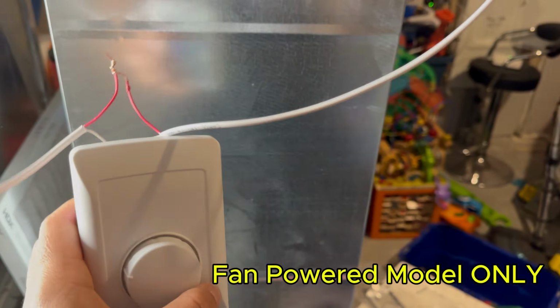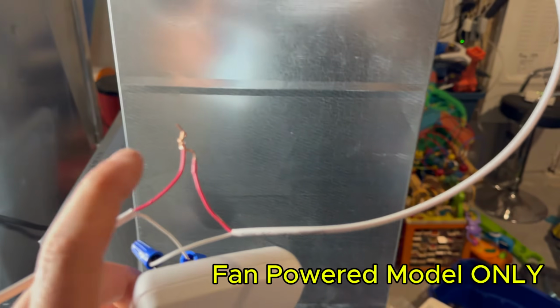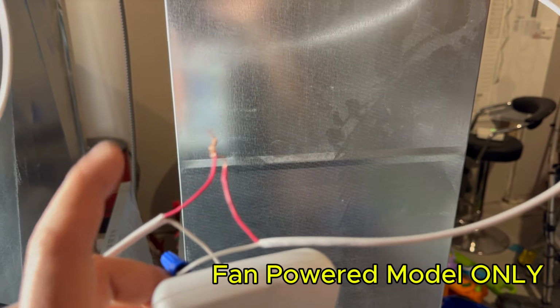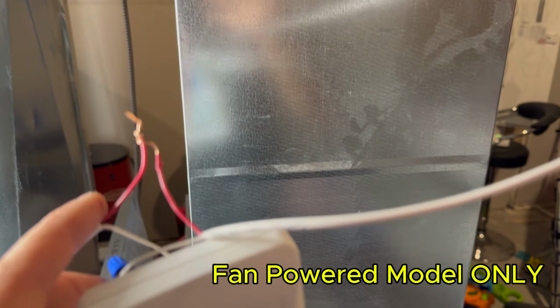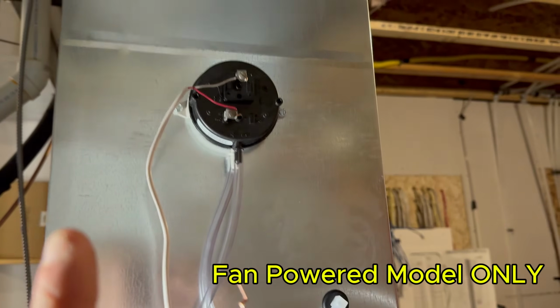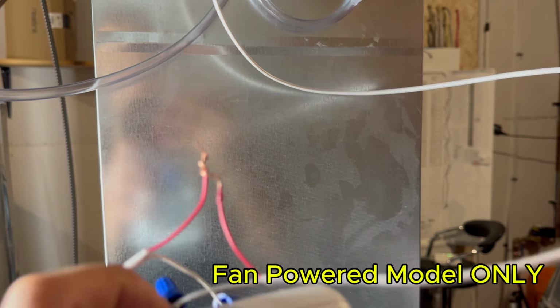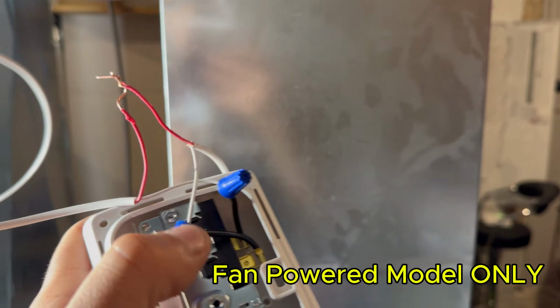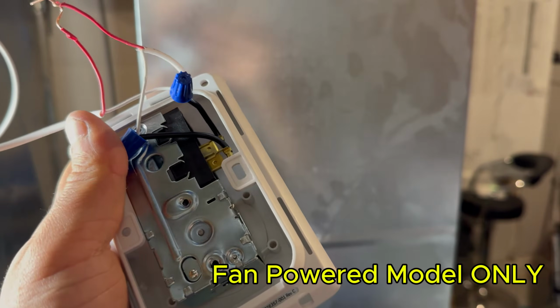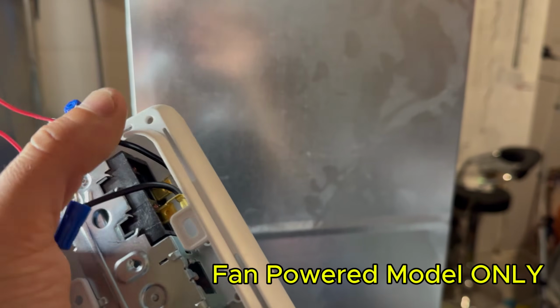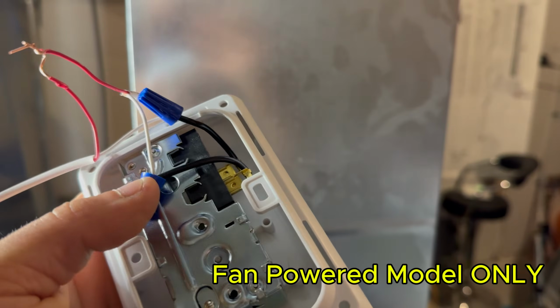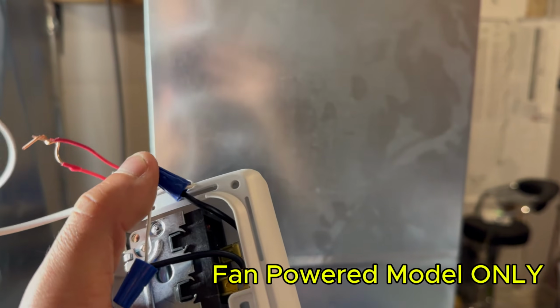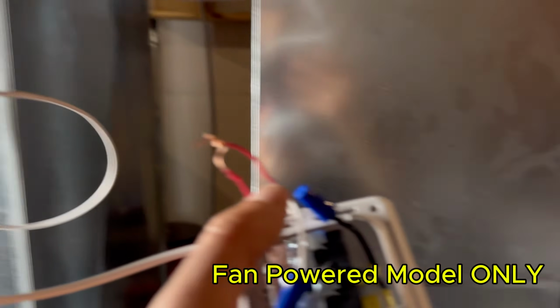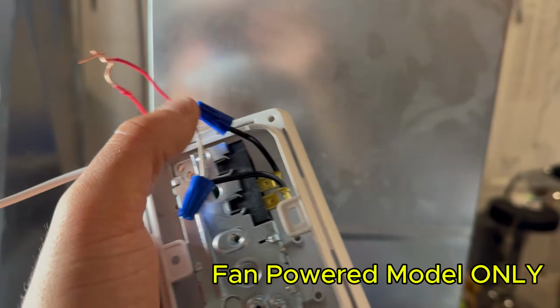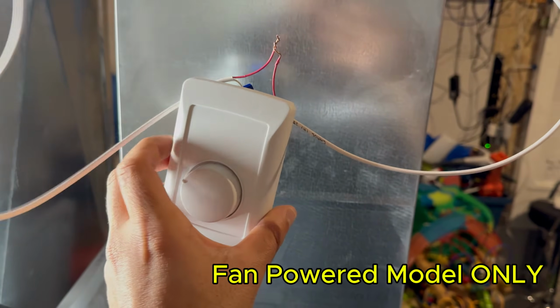It's bridging the connection. So what you'll do is you'll take the 2 red wires from both strands. So 1 red wire coming from the humidifier, 1 red wire coming from the pressure switch, and connect them together. And you'll take one white wire from one strand and connect it to the back of the humidistat. The humidistat has two black wires coming out of it. So one white wire goes to the black, and the other white wire coming from the humidifier goes to the other black wire on the humidistat. And that's all there is to it.